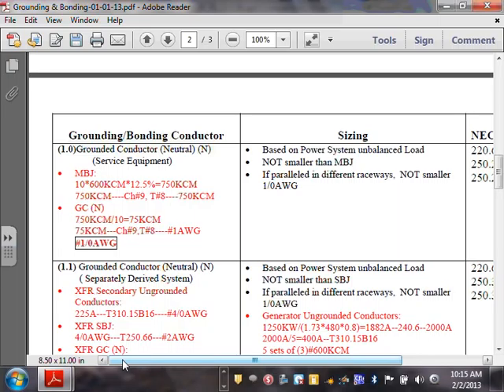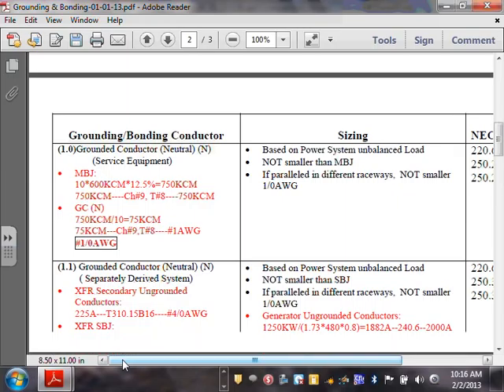So that's the size of my neutral. Neutral's got to be in each conduit. Yes, thank you. When you parallel conductors, each conduit is going to be carrying, in this case, 4 conductors, 3-phase and a neutral. The 3-phase will be 600 kcm, and the neutral will be 1 aught minimum, but you can go higher than that if you want to.